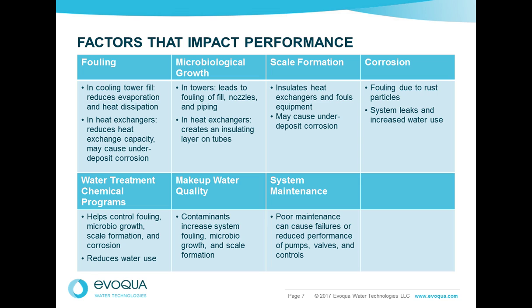The water treatment chemical programs help control fouling and biological growth. You're feeding chemicals to help the cooling system work better. However, if you've got dirt in the system, that dirt can absorb some of those contaminants or chemicals and spoil their effect. Makeup water quality can affect the contaminant load in the system. You put dirt in the system in the makeup water, it concentrates up and becomes more and more of a problem as time goes on.